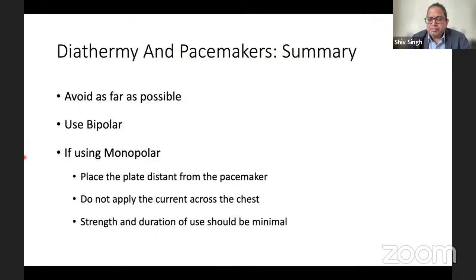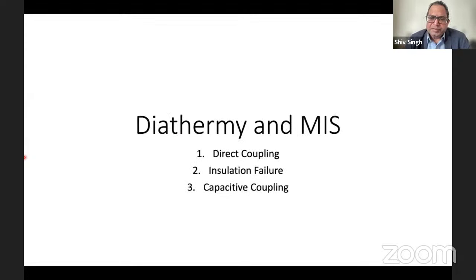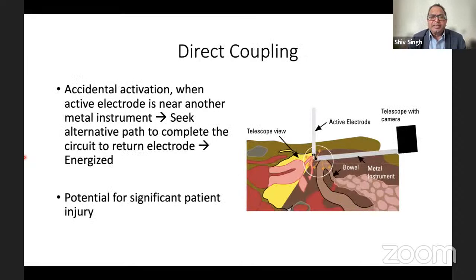Now, diathermy is also used in minimally invasive surgery, and that can be an issue. Problems can happen because of direct coupling, insulation failure, and capacitive coupling. Okay. So direct coupling: accidental activation can occur between the active electrode and any metal part, like hooks or scissors. If they come in direct touch, this is called direct coupling. The circuit can be completed through that.